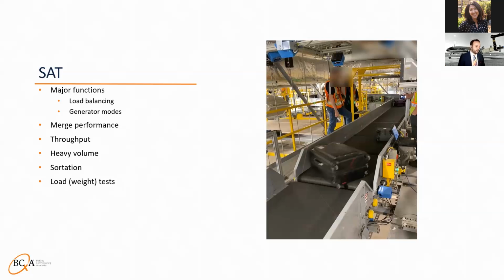And finally, there'll be load and weight tests, or load test as in weight. Sometimes you use sandbags, which is not so great because if they break, you get sand in the bearings. Water jugs are an option, but water can be messy, or cut up rubber gym mats can be very heavy and easy to carry. You'll put those on the conveyors and look for the full load amps and the no load amps and note those down, make sure they match the specs.